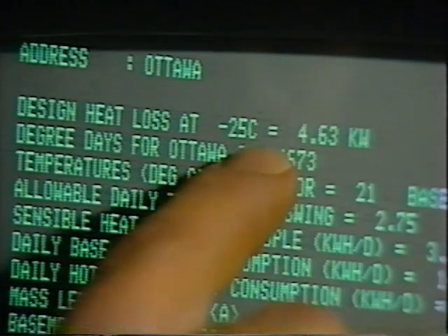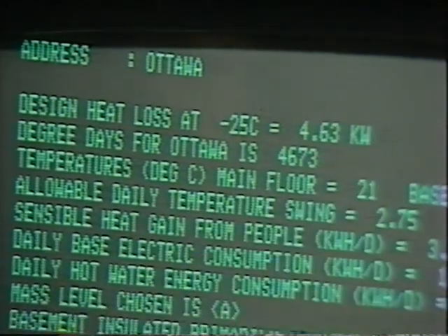David, let me show you how you use the R-2000 to pick a heating system. What you do is you work with the degree days for the area in which you're located, in this case Ottawa at 4,673, and you have a design heat loss, which at minus 25 degrees Celsius is 4.63 kilowatts. It's a lot of words. I just want to try to break them down. Design heat loss, so that means that at minus 25 degrees Celsius, which is the coldest day you're expecting, this house is going to lose 4.63 kilowatts. That's what it's going to require. Which magically then is the maximum amount of heat you'd have to supply, so that's the size of the furnace, 4.63 kilowatts. Not quite the size of the furnace.